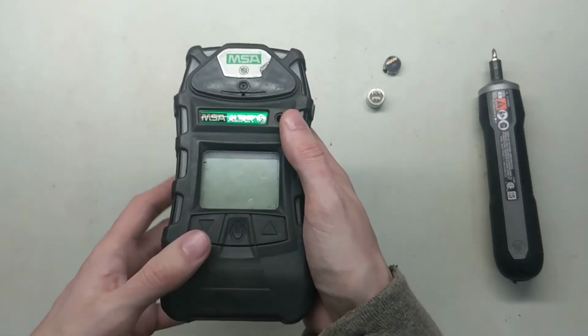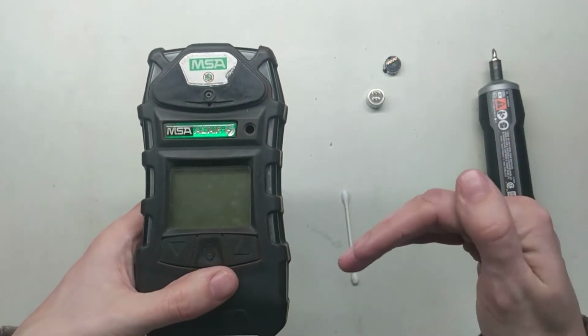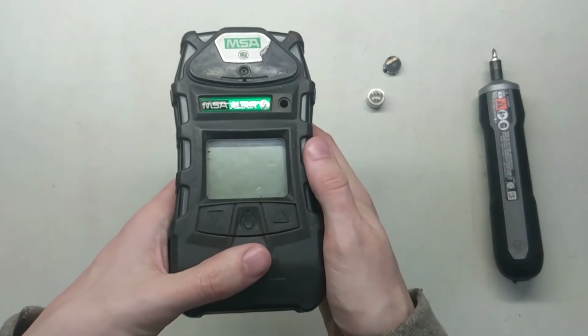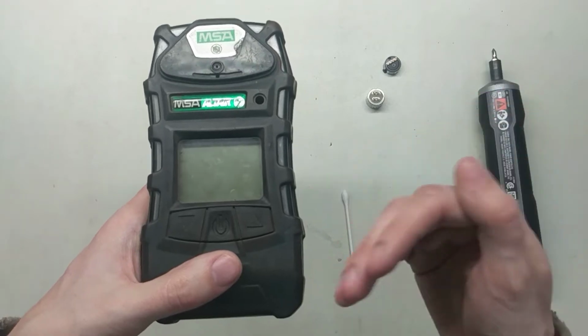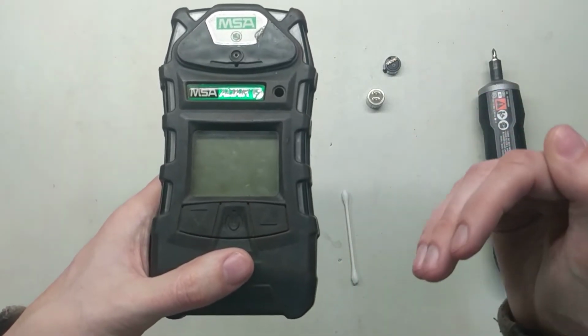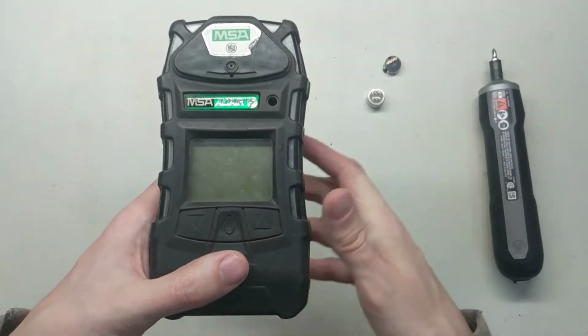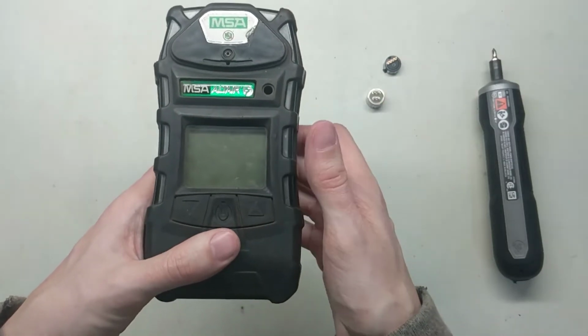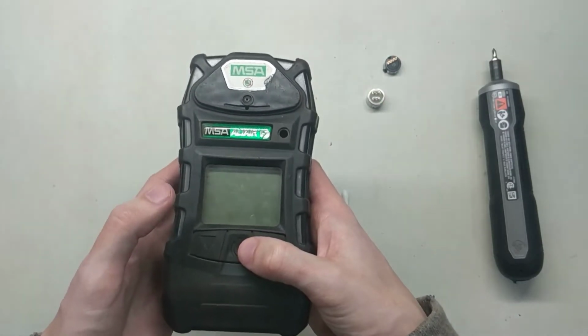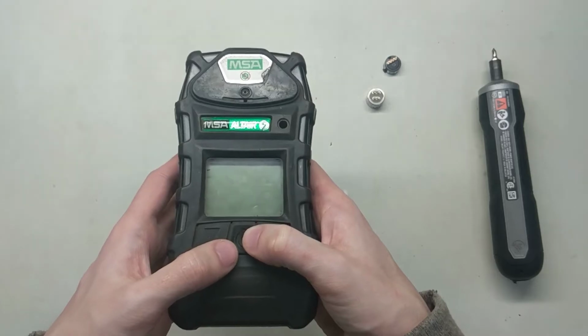You'll watch it when you plug it in, it'll start up super high, showing around 30%, and you'll watch it drop. If you zero it to 20.8 too early, it'll just keep dropping past that and you'll have to keep zeroing it over and over again. So you don't want to deal with that, just let it sit for an hour, then start it up, and give it a zero and a calibration.